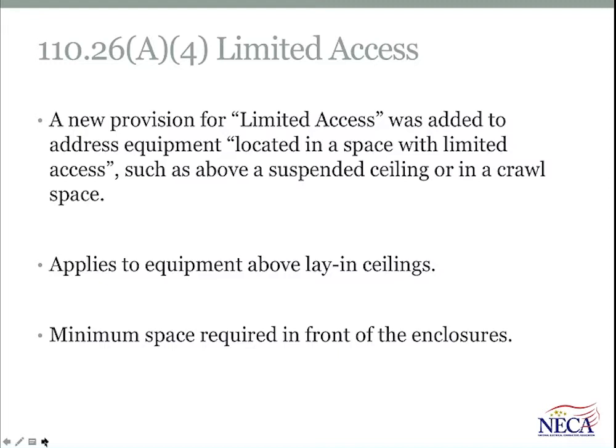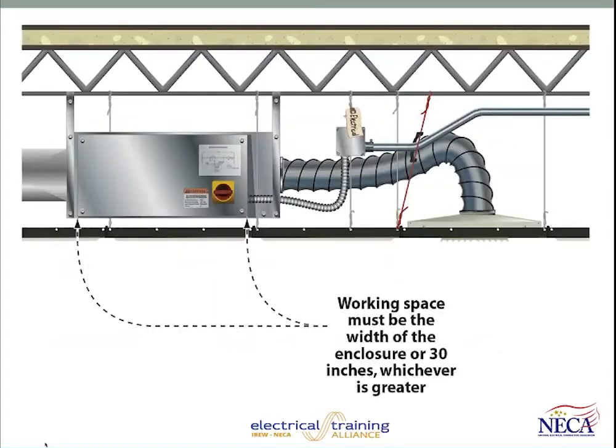And Panel 1 acted favorably to expanding that requirement beyond just duct strip heaters because there's other types of equipment installed in crawl spaces and above suspended ceilings that would require the working spaces specified in 110.26. And the graphic that we show in this program is a Training Alliance graphic from the book as well, but it shows a typical duct strip heater that would require that minimum space for working on while energized. And it's a good example of equipment that's intended to be worked on while energized, especially in a troubleshooting mode.